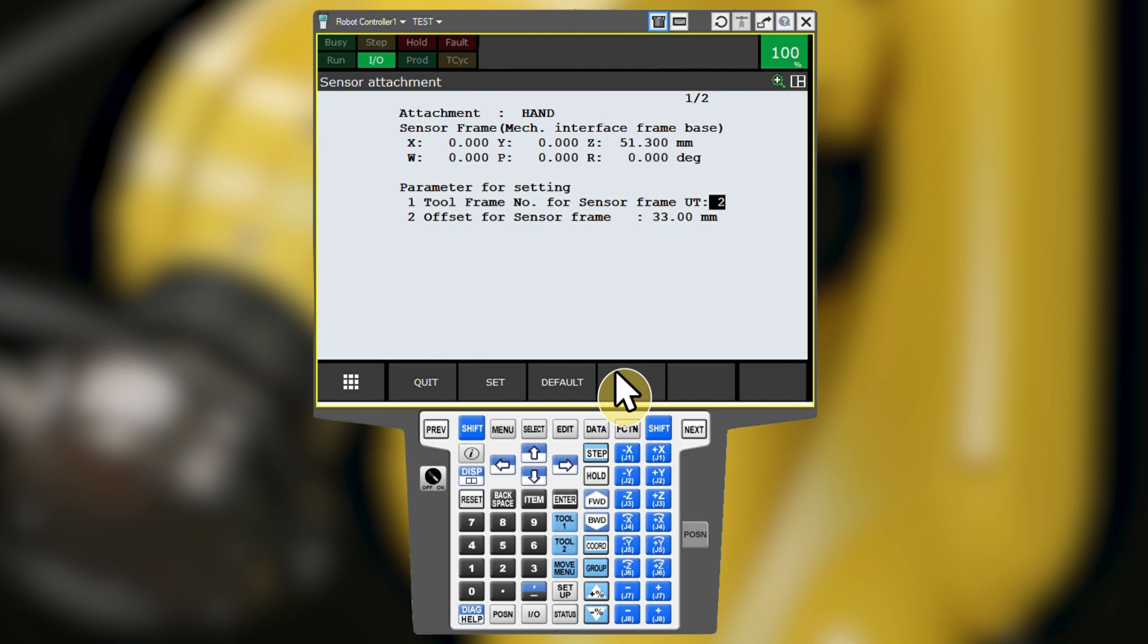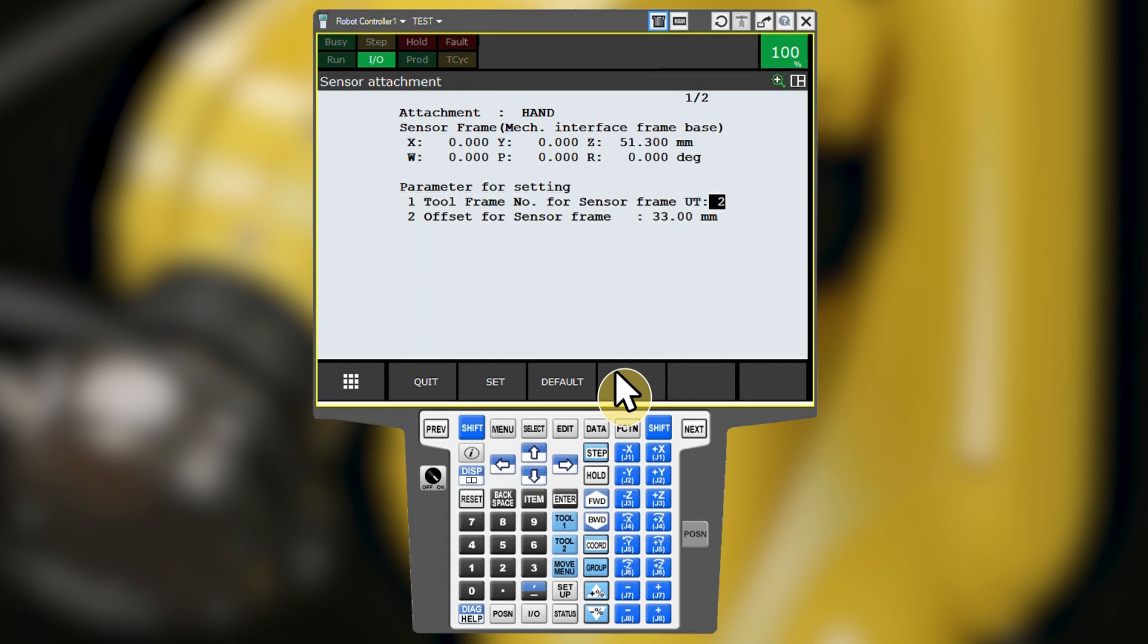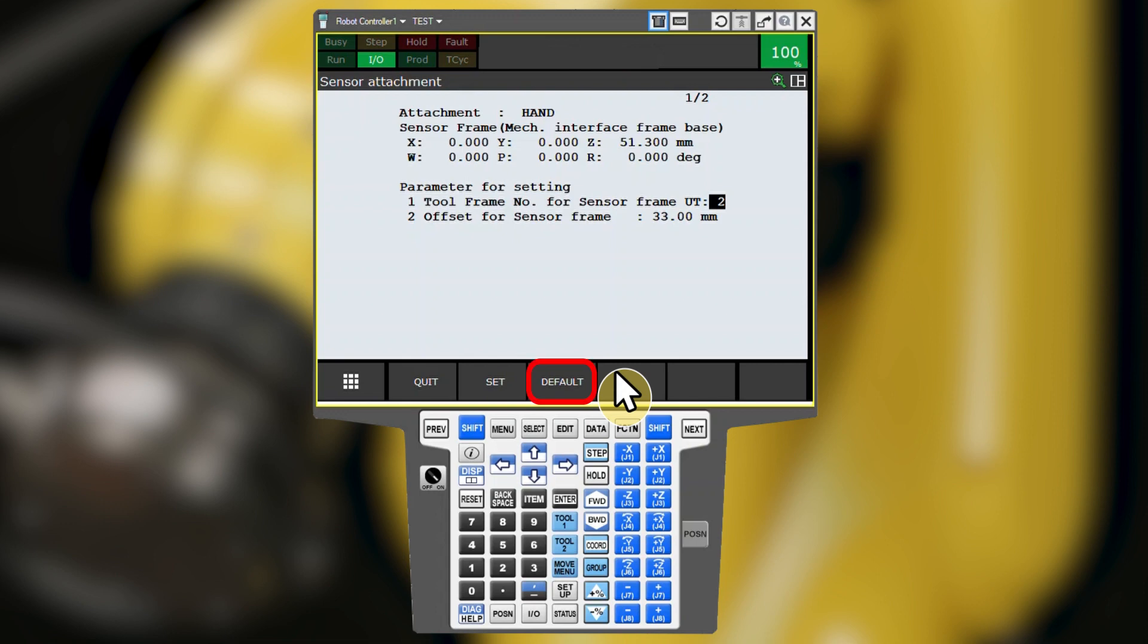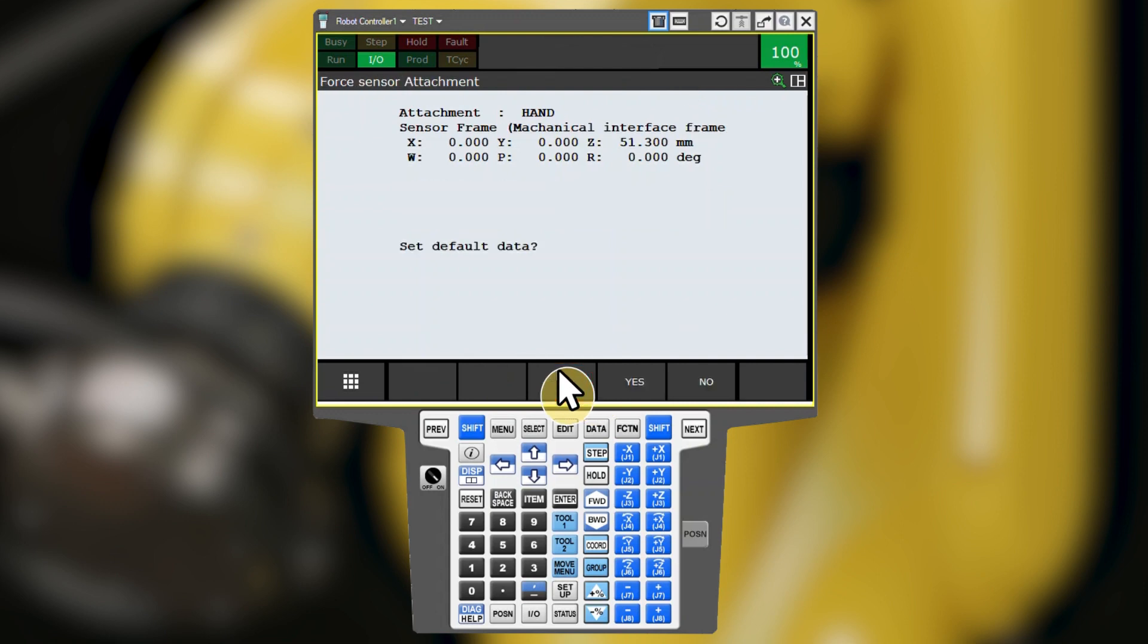With ATI FANUC Ready kits, the sensor frame is pre-programmed onto the sensor to match the interface plate it was sold with. The sensor frame values will automatically be populated into the sensor frame definition here. You can also press F3 for default to reread the pre-programmed values off of the sensor. If you are using the ATI FANUC Ready kit and the pre-programmed sensor frame values, go ahead and press F3 for default, then F4 for yes, then F4 for yes again.